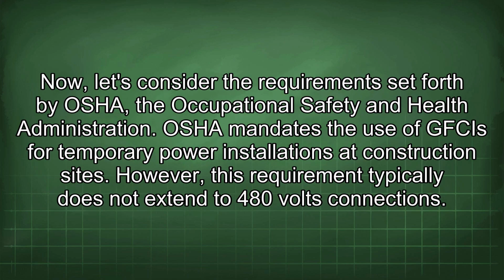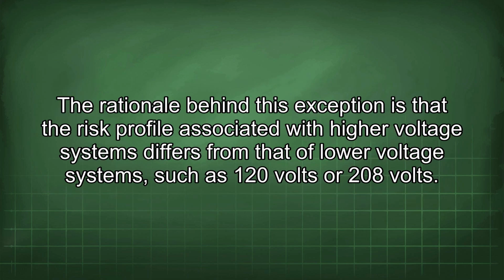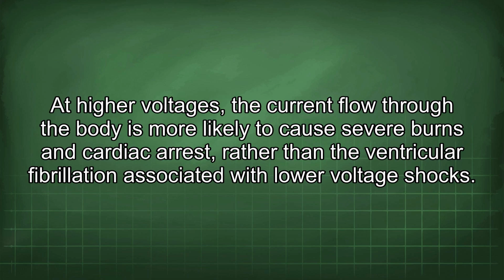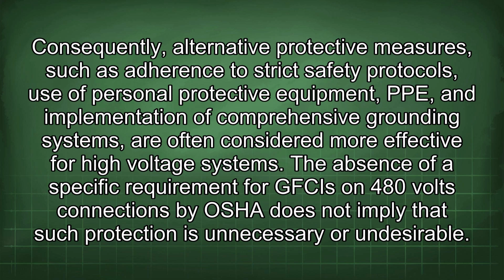Now let's consider the requirements set forth by OSHA, the Occupational Safety and Health Administration. OSHA mandates the use of GFCIs for temporary power installations at construction sites. However, this requirement typically does not extend to 480 volt connections. The rationale behind this exception is that the risk profile associated with higher voltage systems differs from that of lower voltage systems, such as 120 volts or 208 volts. At higher voltages, the current flow through the body is more likely to cause severe burns and cardiac arrest, rather than the ventricular fibrillation associated with lower voltage shocks. Consequently, alternative protective measures, such as adherence to strict safety protocols, use of personal protective equipment, PPE, and implementation of comprehensive grounding systems, are often considered more effective for high-voltage systems.